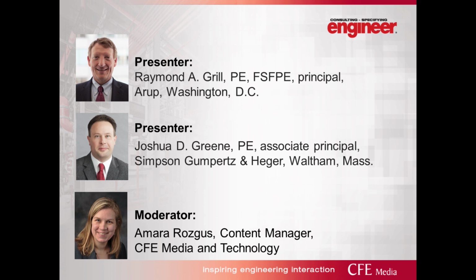And so this would be a standalone parking structure that typically does not need fire alarm, but elevator recall is required. As I mentioned, the elevator codes require recall for an elevator that extends more than 1 story. So the fire alarm panel would typically be provided for detection. Now, if it's an outside environment, the code allows you to put heat detectors in those lobbies for recall in lieu of smoke detectors, because the smoke detectors would typically be outside their range of humidity levels and temperatures in most climates. But that panel is what NFPA 72 calls a dedicated fire alarm panel. It's specifically defined in 72, and additional fire alarm devices are not required. It is just there to provide the elevator recall function.